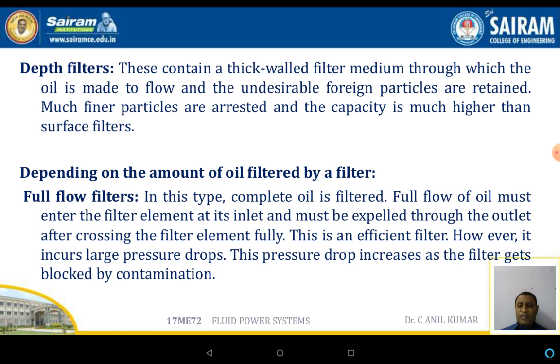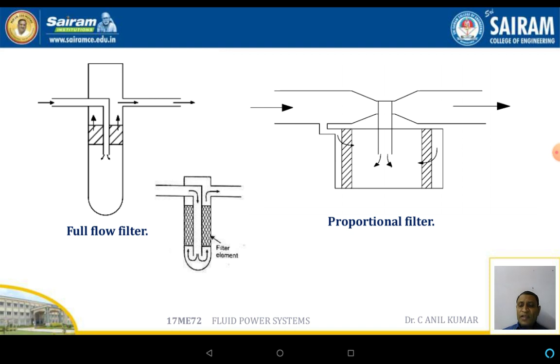Depending on the amount of oil filtered, filters are also classified as full flow filters. In full flow filters, the complete oil is filtered. The full flow of oil must enter through the filter element at its inlet and must exit through the outlet after crossing the filtering element before passing to the application end. This is an efficient filter; however, it incurs a large pressure drop, which increases as the filter gets blocked or contaminated.